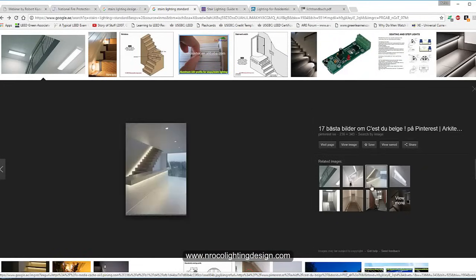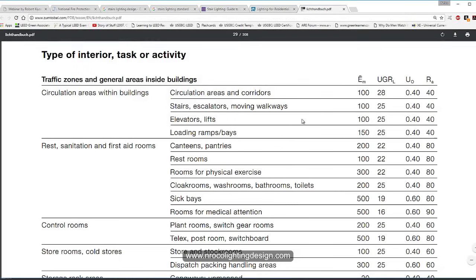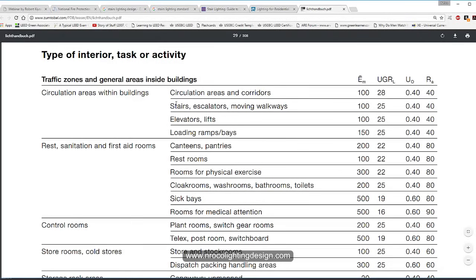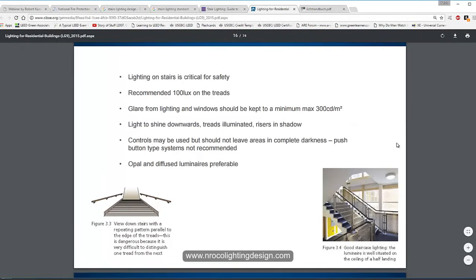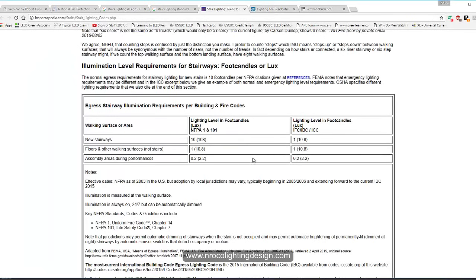If it's for the fire exit staircase or for security, we need to calculate it according to the standard — it should be at least 100 lux, UGR 25, uniformity 0.4, and Ra 40. For fire exit stairs, at least 100 lux is recommended for the treads. In our office, following NFPA (the fire code), they require at least 10 foot-candles, or about 108 lux.